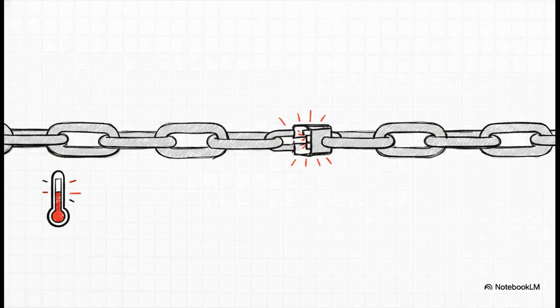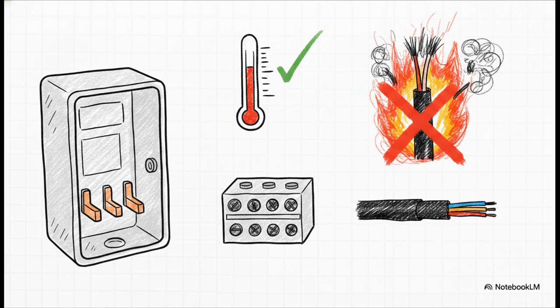You know, you're only as strong as your weakest link. So you're very often forced to limit your calculations as if that wire is only rated for 60 degrees. So why exactly do we do this? Well, for small HVAC branch circuits, our connection points are often physically limited to 60 degrees. We're talking about the disconnect plugs, the equipment terminals themselves, or even specific limitations of the cable type. Like if you're running NM cable, Romex.